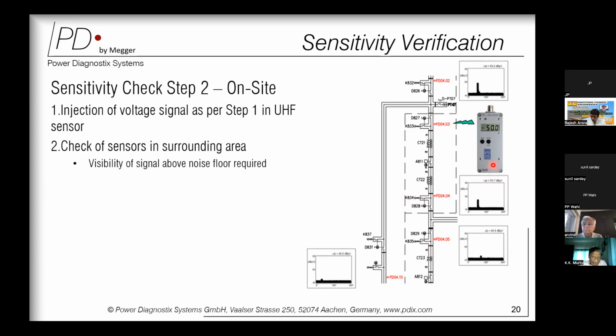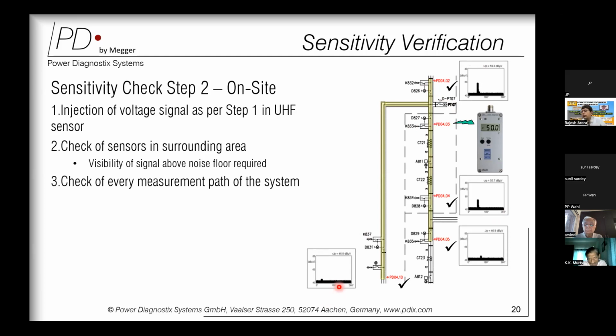It is not that it has to read exactly the same amount of amplitude, but it should react to this particular pulse. That is the first criteria, and it is again extended to the next nearby sensors. This way we have to check every measurement path of the GIS.